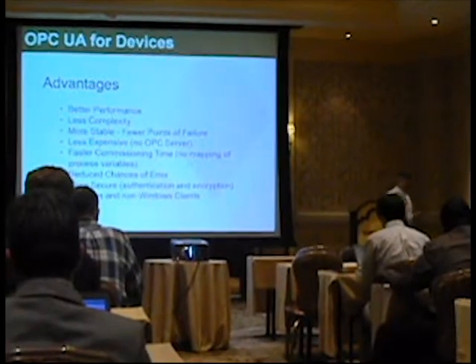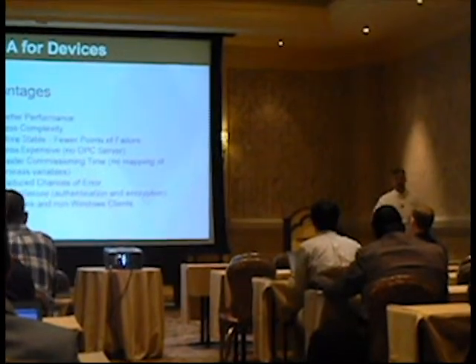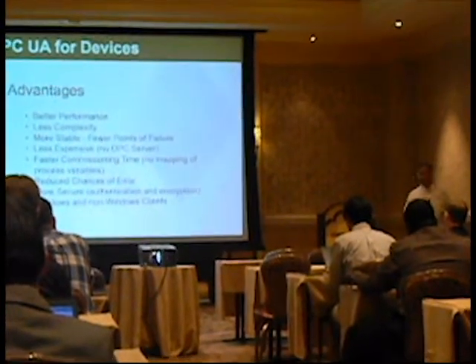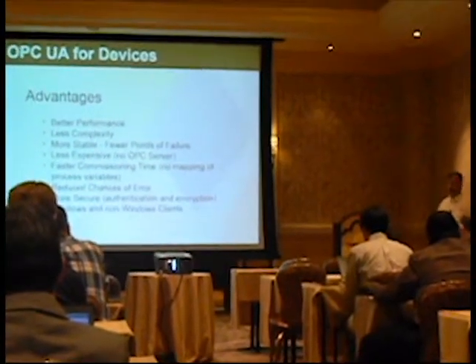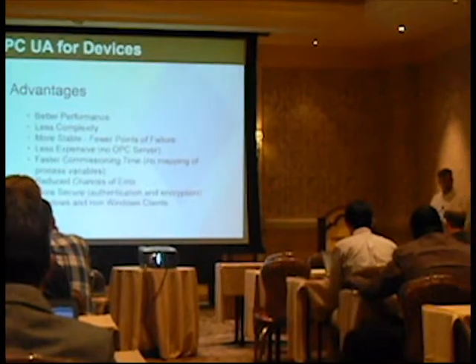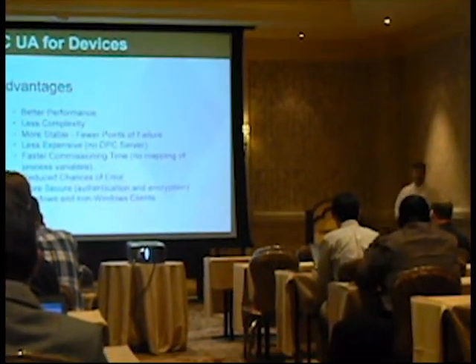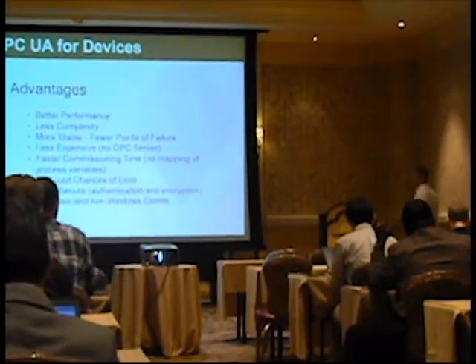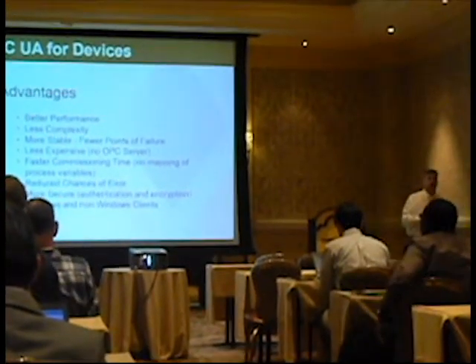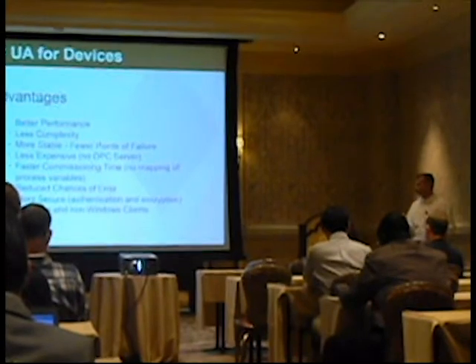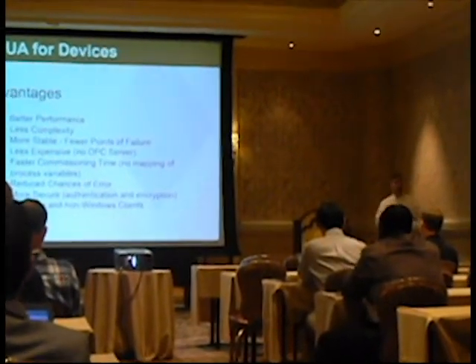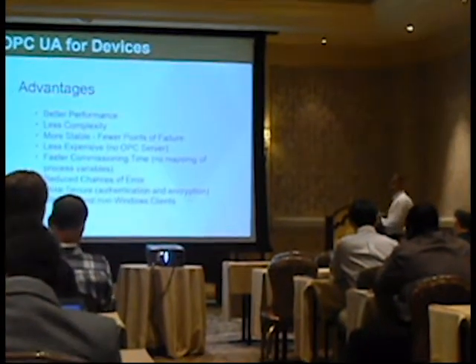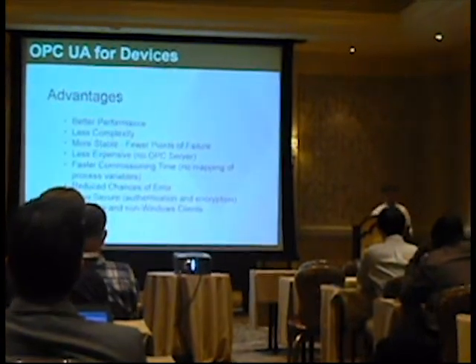Having an OPC UA server on the hardware gets rid of some software — we don't need the OPC server anymore, we don't need proprietary drivers. As soon as there's less software, a bunch of things jump out at you: you're going to get better performance, there's less complexity, there are fewer points of failure, and you're going to have a more stable system. It's less expensive — you don't have to go buy an OPC server, and with fewer pieces of software to configure, it's cheaper to deploy. The systems we end up with are also more secure. The OPC UA server talks encrypted to the clients, and to communicate with it, you need to authenticate yourself. And of course, OPC UA runs on Windows and non-Windows platforms.